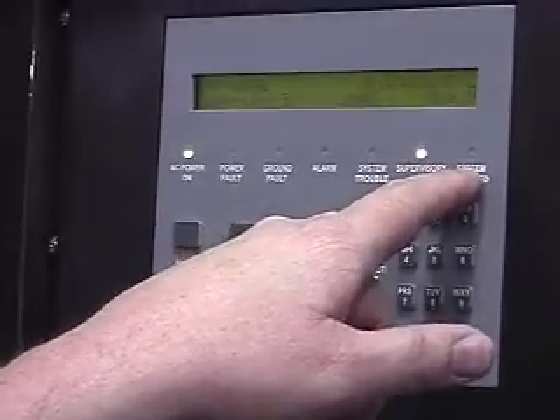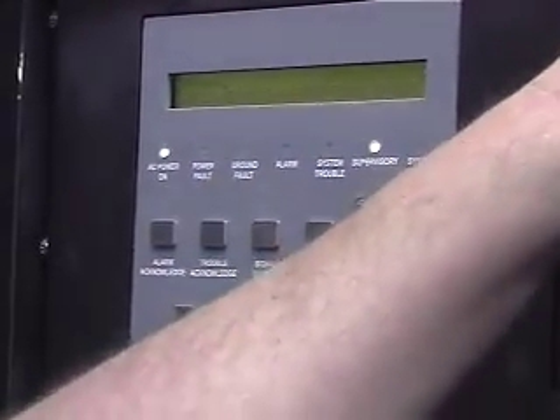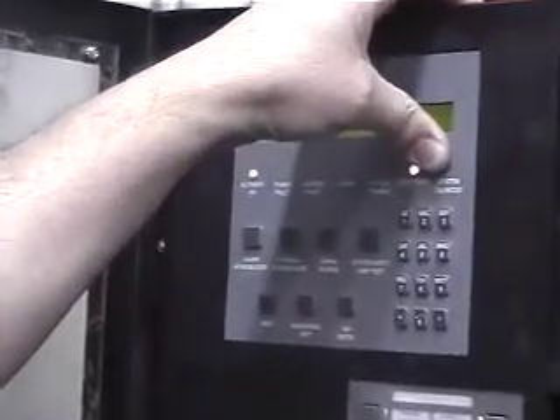But when you press signal silence, this light will come on. It may not silence right away because it has to go through the full message. So if you press silence when it starts the first part of the message, it'll keep going until it finishes the message before it repeats. Once this light's on, you'll know it's done its sequence, but it might take a few more seconds for the message to fully complete before it silences. So don't panic and keep pressing it, because you're just going to deactivate it. Just press it once, watch the light go on, and then once that message fully completes before it repeats, it silences.